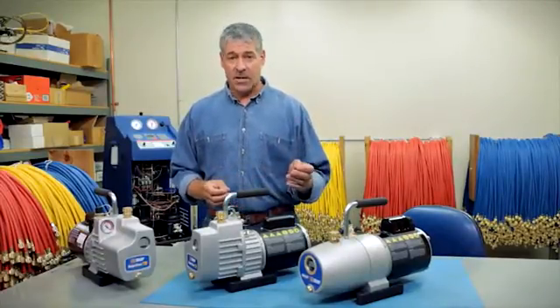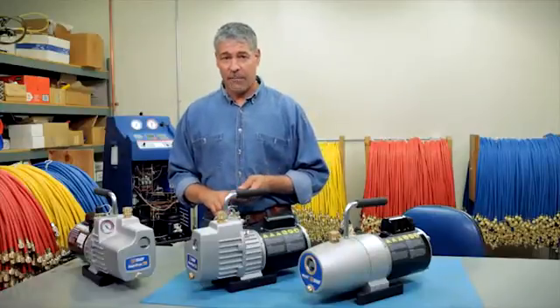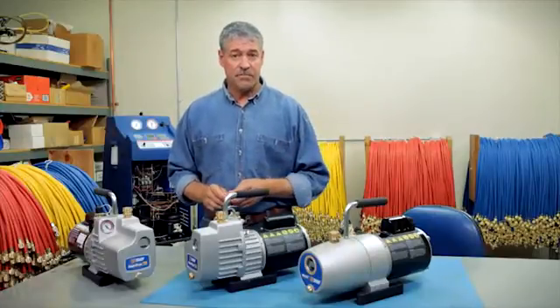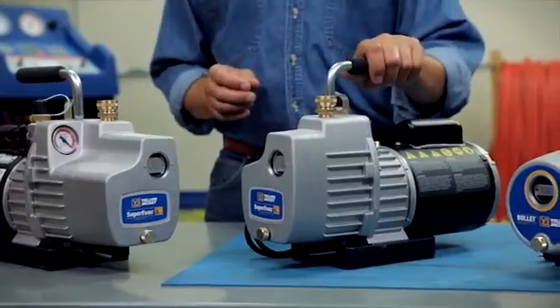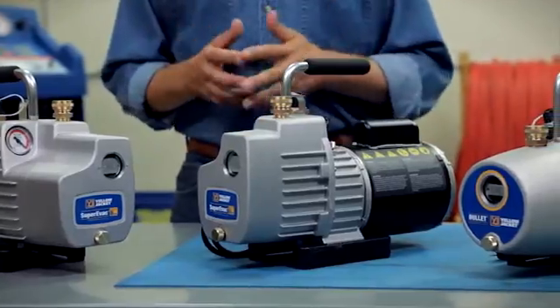This makes them very sensitive to moisture and other contaminants which can freeze up the system, corrode the metals, and sludge the oil — the cause of most problems and complaints when a system stops working. Therefore, it's extremely important to remove moisture with a quality vacuum pump before the critical charge takes place.